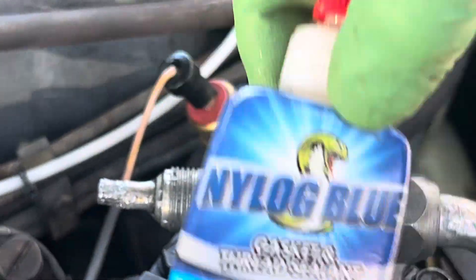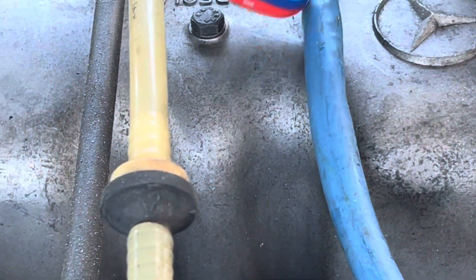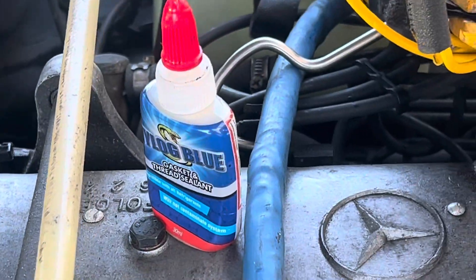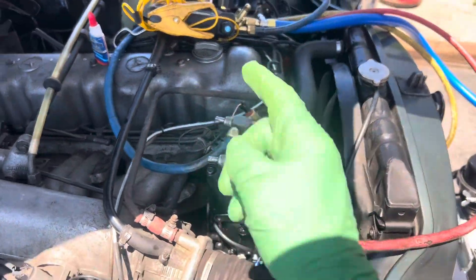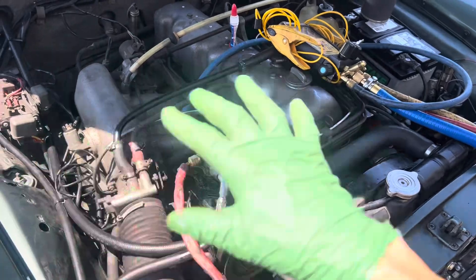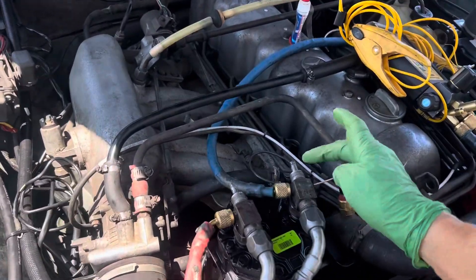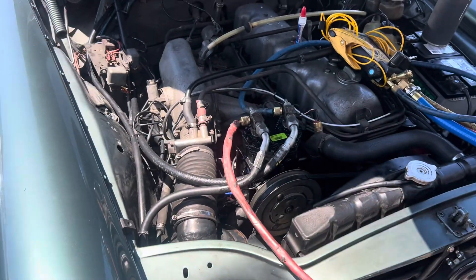By doing this, vacuum cannot pull through the Nylog. This is specially made for vacuum — to stop vacuum. It never gets hard; it's made out of refrigerant oil so you're not going to contaminate anything. If you don't have that — because you're in another country or it's stupidly expensive to order — silicone grease, spark plug grease, dielectric grease. Every country has that. Put a little dielectric grease in there and vacuum cannot pull through dielectric grease.